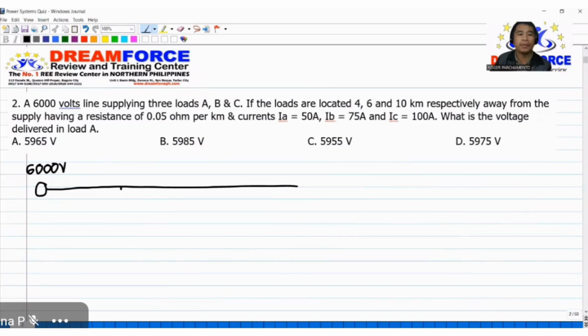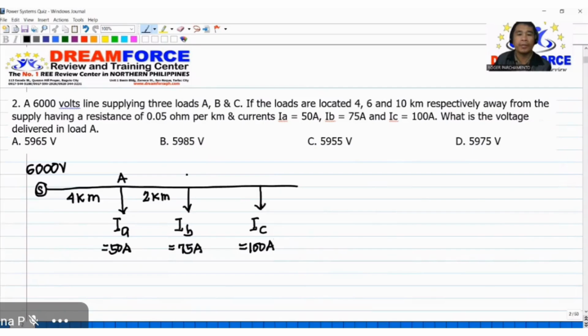It's just a straight line. So at 4 kilometers from the source, we have a drawn current of IA that is equivalent to 50 amperes. Then at 6 kilometers, which is of course 2 kilometers from A, this is IB, equivalent to 75 amperes. So this is 2 kilometers. Then we have 4 kilometers. Then at C, that is 10 kilometers from the source, we have IC equivalent to 100 amperes. Then this is B, this is C. So what is the voltage delivered in load A?